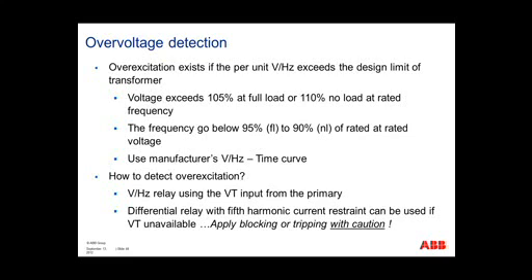Overexcitation exists if the per unit volts over hertz exceeds the design limit of the transformer. The voltage exceeds 105% at full load or 110% no load at rated frequency, or if it goes below 95% full load, 90% no load at a rated voltage. Look at the manufacturer's time curve to determine if you need to block or trip during this overvoltage condition.